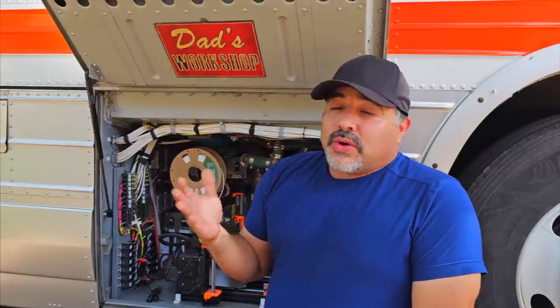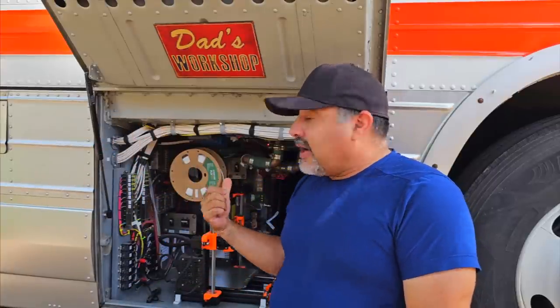Given all those things, it would be wise to have a cooling solution we could depend on that would actually work. The air conditioner has been in now for four years and it has worked great. We don't run it all the time — if it's in the seventies outside we're not going to run it. We do have temperature monitors, both external and in our BMS, that tell us exactly what the temperature is. The other added benefit is it removes humidity. Any humidity that finds its way in will be removed, and there's a hole in the bottom where condensate can drain down onto the ground.